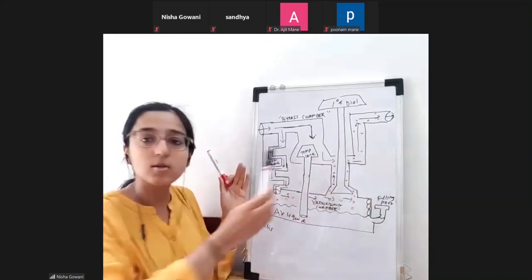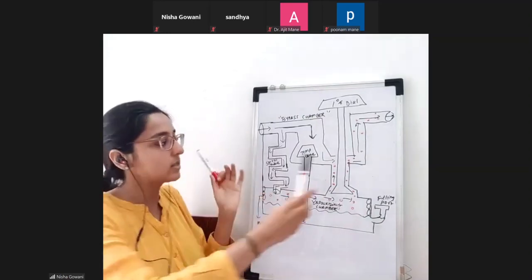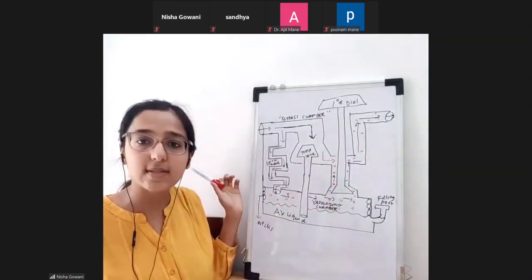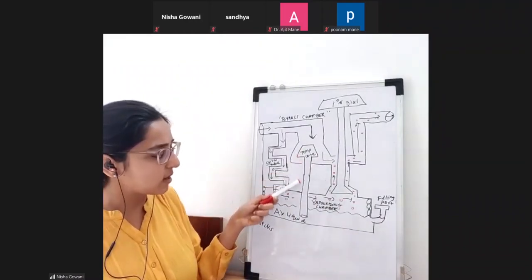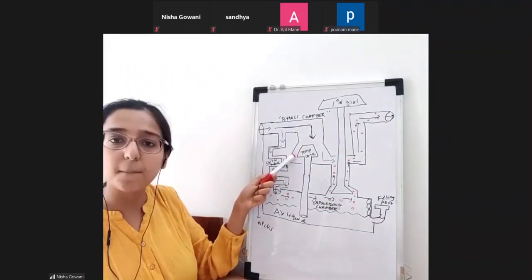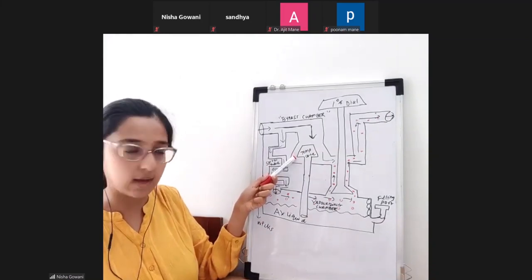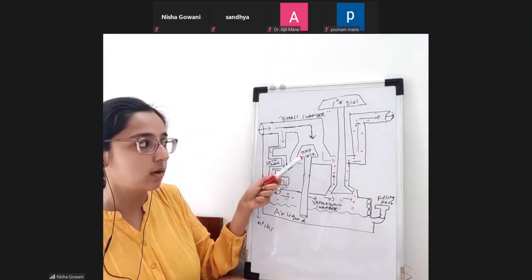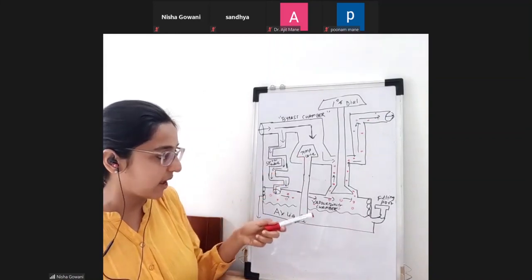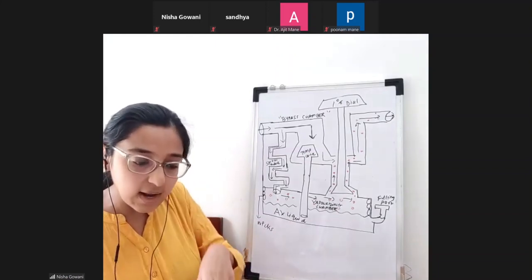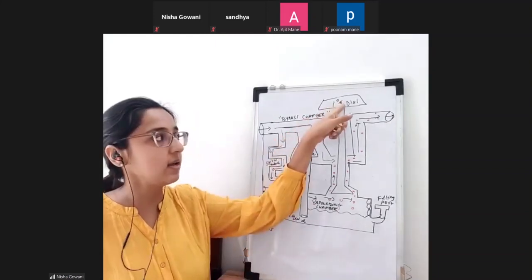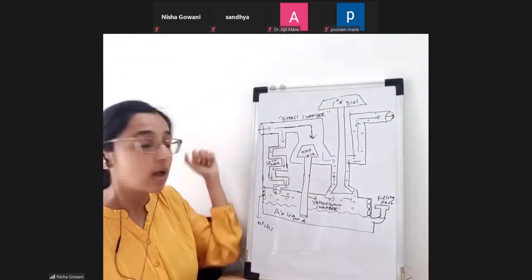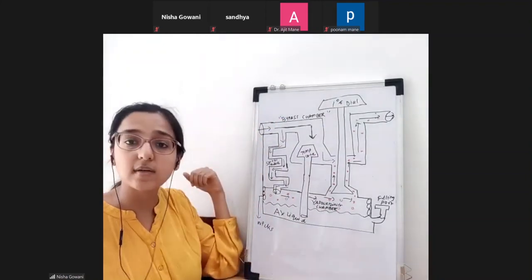So the overall gas is joining over here, and now it will exit and go towards the patient. I have drawn something like a cone over here. This is known as a temperature compensating cone. We'll understand what the role of this cone is and what it does in a little bit of time. Next we'll understand what this dial setting is, and who decides how much gas will go in the bypass and how much gas will go down towards the vaporizing chamber.